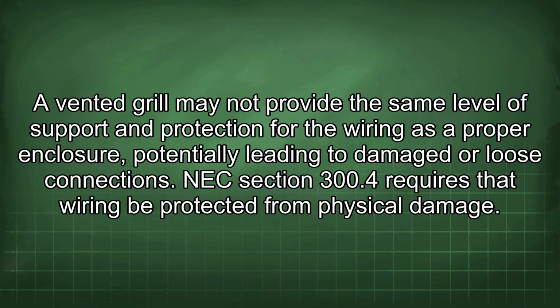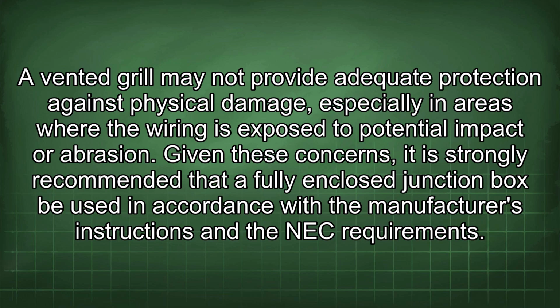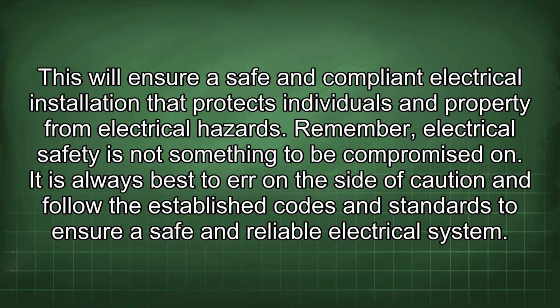NEC Section 300.4 requires that wiring be protected from physical damage. A vented grille may not provide adequate protection against physical damage, especially in areas where the wiring is exposed to potential impact or abrasion. Given these concerns, it is strongly recommended that a fully enclosed junction box be used in accordance with the manufacturer's instructions and the NEC requirements. This will ensure a safe and compliant electrical installation that protects individuals and property from electrical hazards.